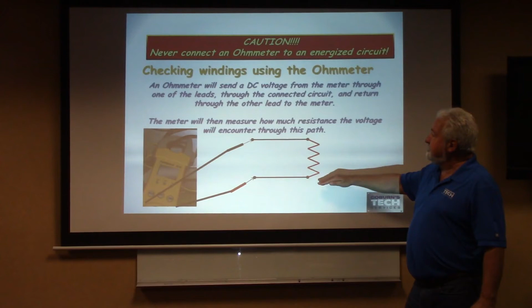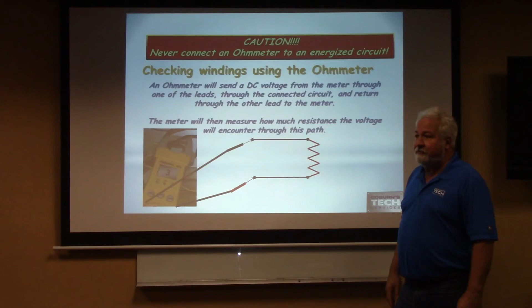Check the windings using an ohm meter. An ohm meter will send DC voltage from the battery that's inside that meter through whatever it is you're trying. What kind of load is this? A resistive load. Is that right? Resistive load is going to produce heat. Good, very good. So this might be a heat strip we're checking. Is that right? So we're going to send voltage through there and then back to the meter. The meter will then measure how much resistance is in that path. And when it does that, maybe it's 3 ohms of resistance. Everybody good with that?